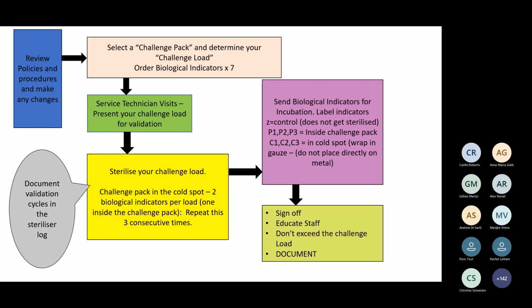Then you're going to sign off. Once you've done your validation, you'll get all your paperwork back from the technician who did your validation, and you're going to sign off, educate your staff, don't exceed the challenge load that you've given the technician, and document everything that's happened. Also document your validation cycles in the sterilizer log.